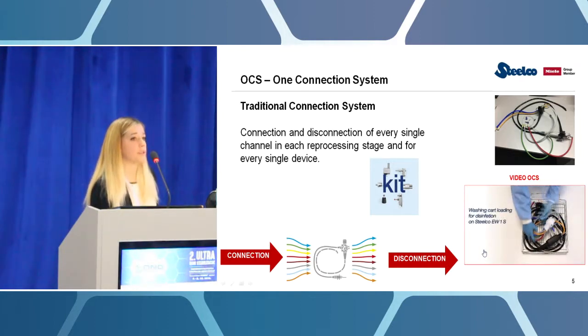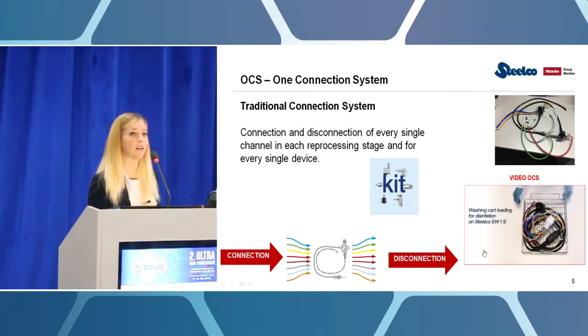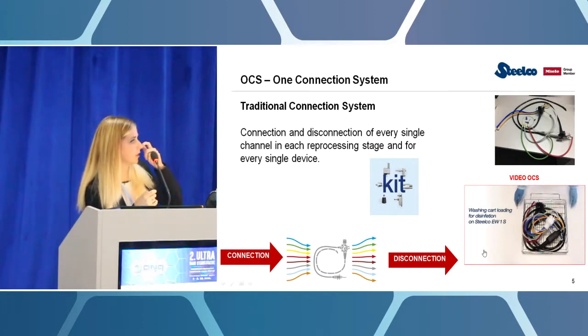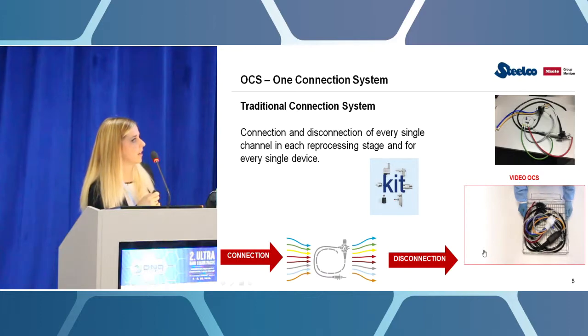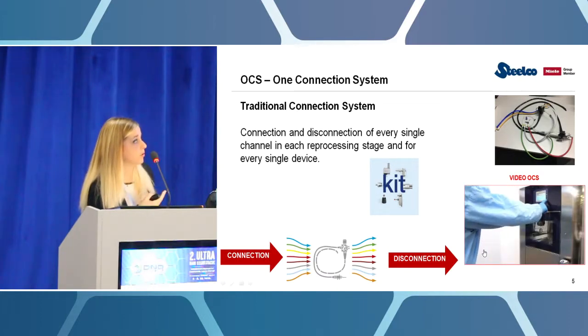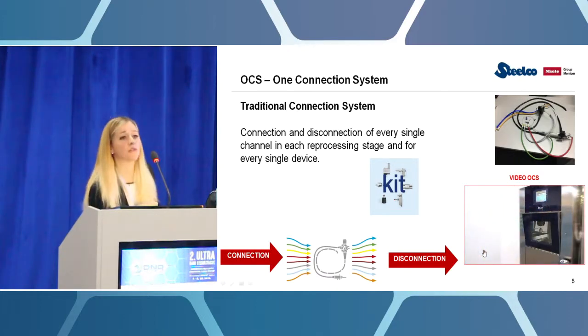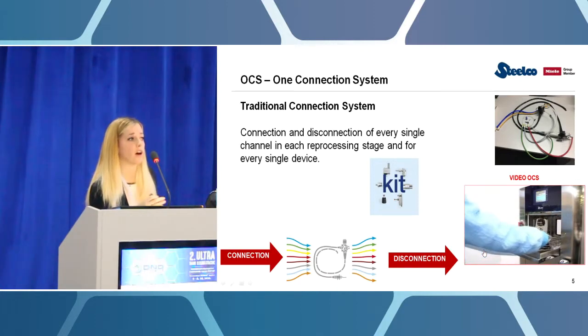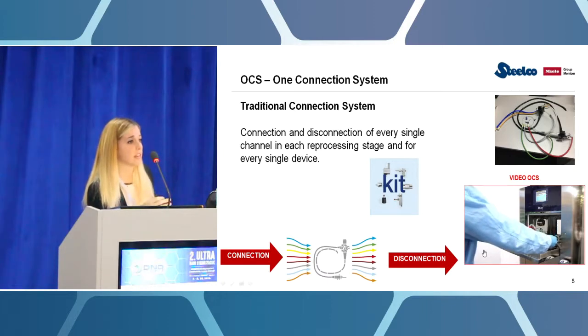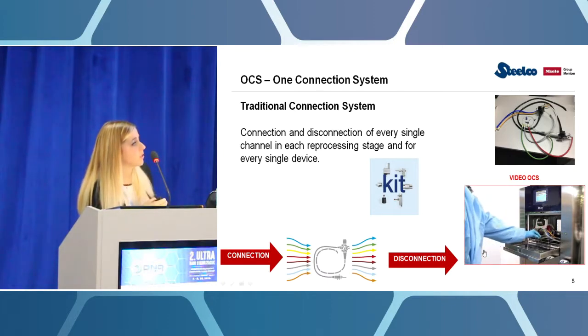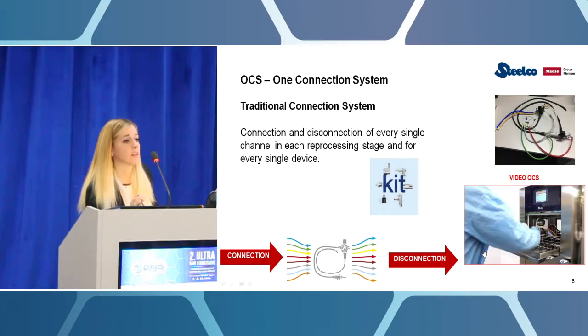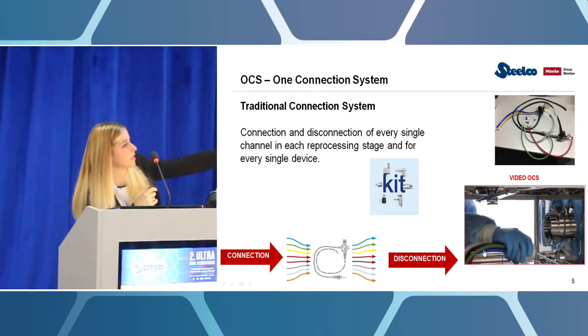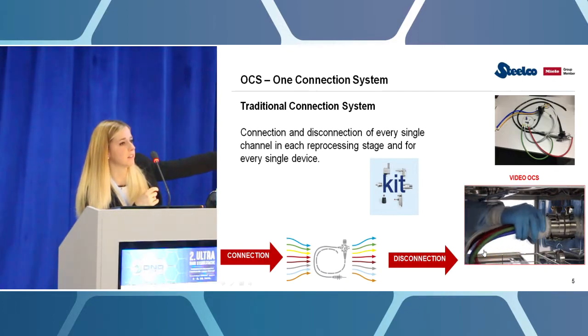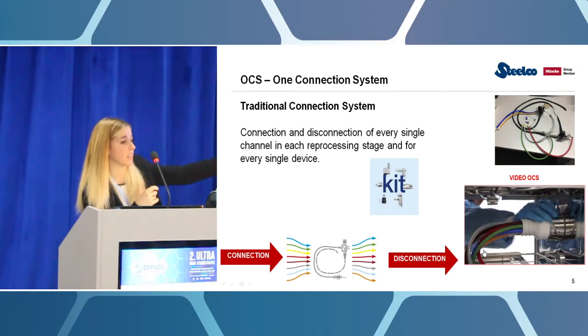So you basically do this activity now at the very beginning of the process, and then you're done. You put your scope inside a mesh tray, and you move inside the endoscope washers. And all of them, regardless of their capacity, have the same connection system. So you see, you're not touching the scope anymore. You're basically using that part of the connector, the white part, and you connect it to the side of the machine.